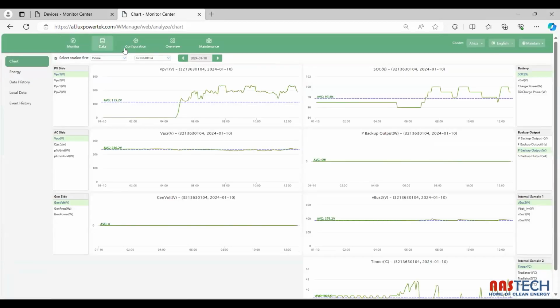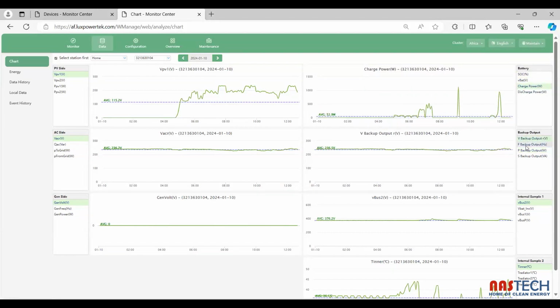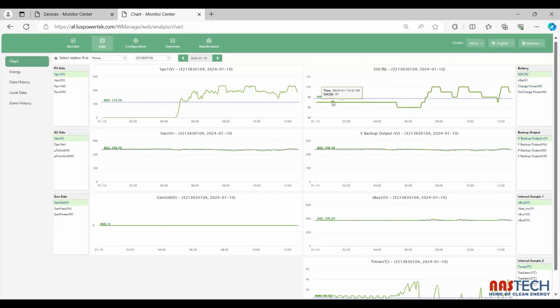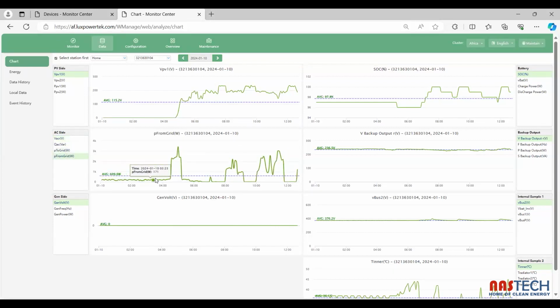As I was taking you through the tabs, I'm going to get to the very last tab. The very last tab is the maintenance, where you do the settings. The data tab is all the charts and event histories of the device. You can see all the energy: the PV side, AC side, generator side, battery. You can toggle between each of these, and it will give you the data. You can sometimes see the battery energy in relation to when there was load shedding in our country, so power from grid. You can see sometimes when the grid goes flat, there's no power that the grid is giving. So if you're completely off grid, you will see power from grid will be a flat line from start to end.